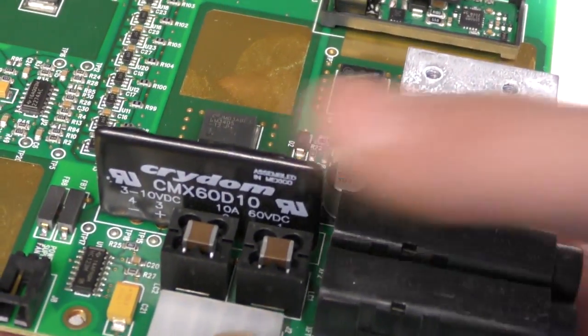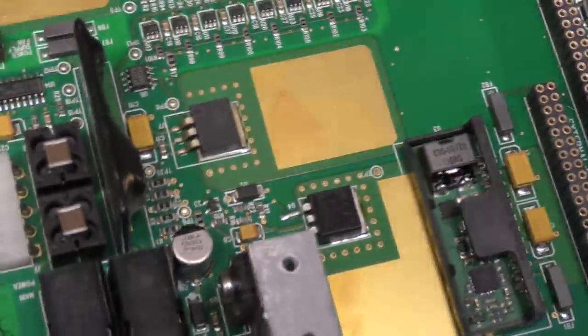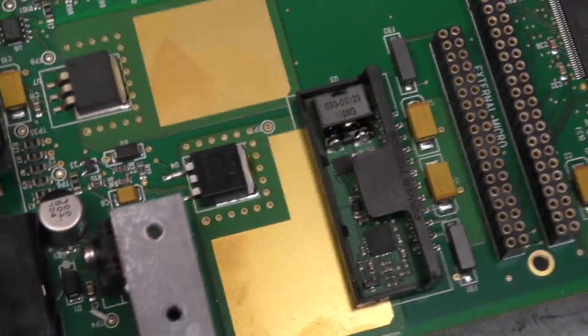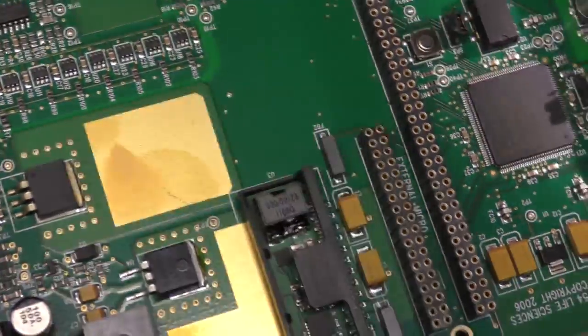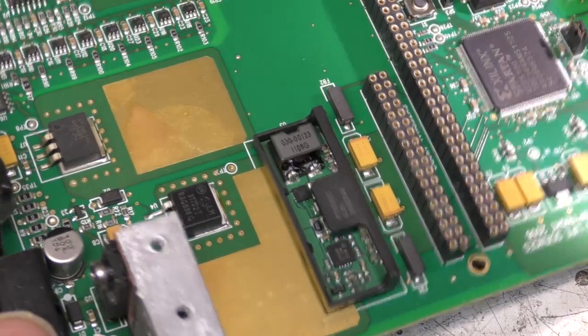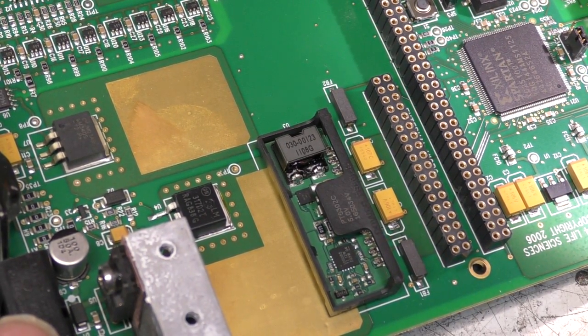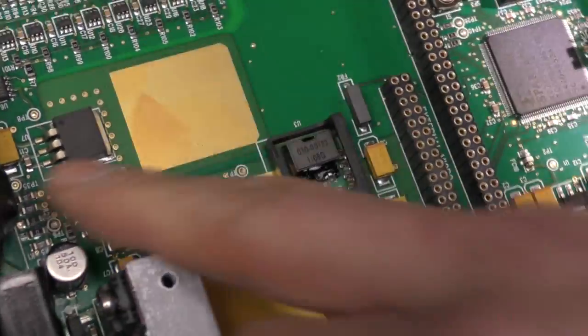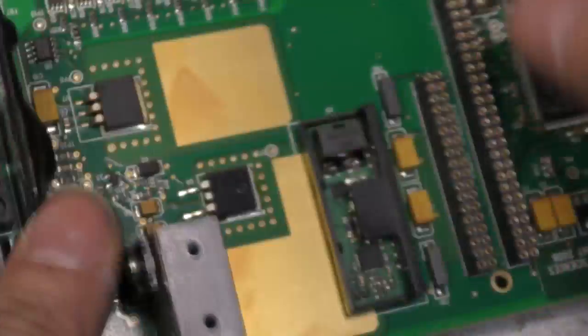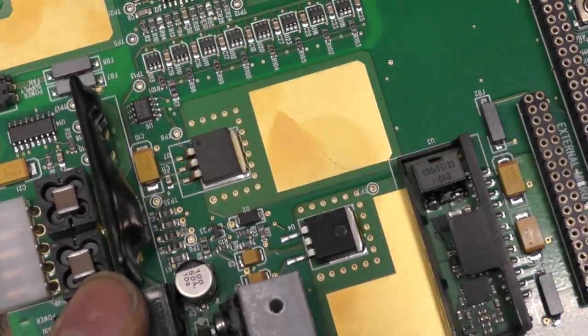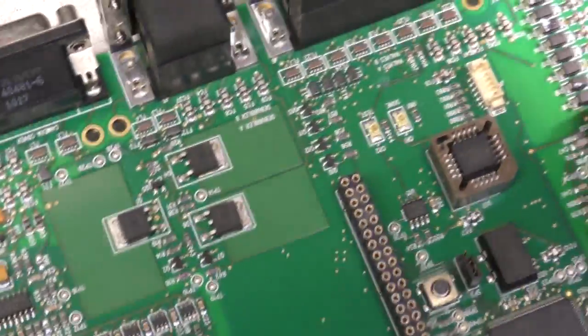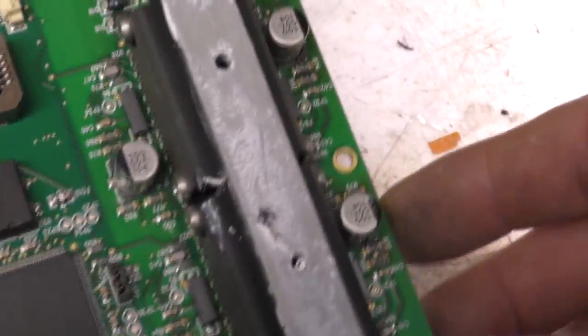One thing, there's a 10 amp solid state relay on there. I wonder if that might be controlling the power to the Peltier cooler on that unit by the reagent tube. I can't think what else it would want to switch on and off that would need a significant amount of power. I can't really be bothered to trace out where that goes. So, just a few various linear regulators. Again, lots of filtering on the IOs, and filtering and back EMF protection on the stepper motor outputs.